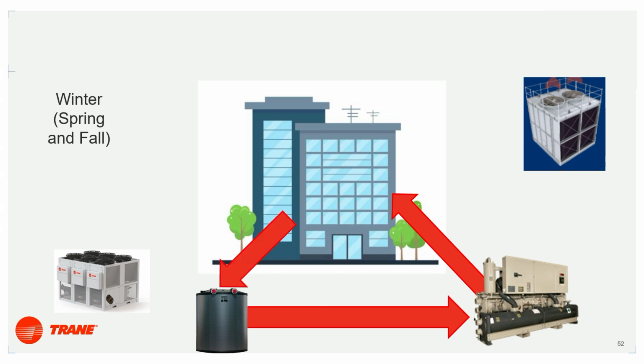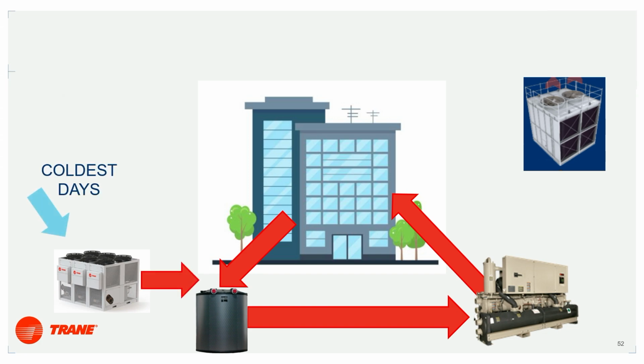We're talking about smaller tanks and footprints, obviously an issue everywhere. As that load increases and the cooling load drops throughout the day, we're going to reject that heat out of our building because we've already cranked down our air side economizer. We're going to use that to recharge that battery. We are going to cool our building with the ice in the tanks while also providing heat out of our chiller heater, heat pump. On the coldest days, we're going to need additional heat source, right? It's not going to be enough.